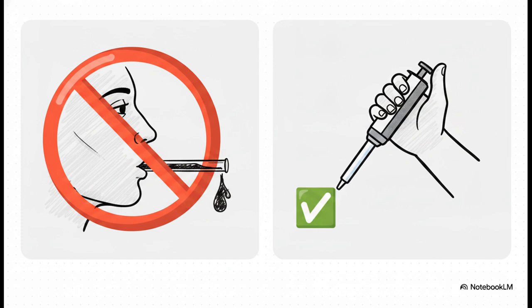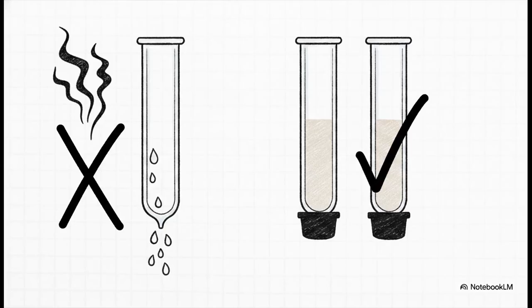But here's the real kicker. Just having those rubber bulbs sitting in a drawer isn't enough. The staff actually has to be trained on how to use them. On a similar note, open-ended butyrometers, the ones used in the Gerber method for determining fat content, are a massive accident waiting to happen. Because they're open on both sides, there's a huge potential for spilling highly concentrated sulfuric acid and amyl alcohol right onto the technician, not to mention releasing corrosive fumes into the air.